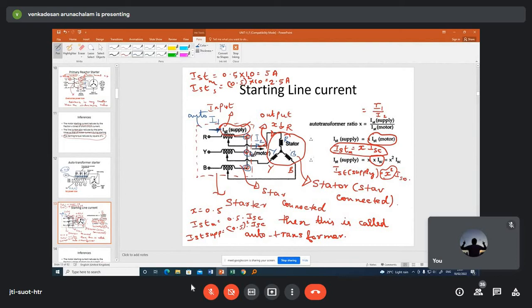So I1 is the line current or supply current, and I2 is the motor current. So what is the auto transformer turns ratio? X is nothing but I1 by I2. I1 is the input current to the auto transformer, that is the line current, that is the starting current, and I2 is the output current from the auto transformer, that is the input current to the motor.